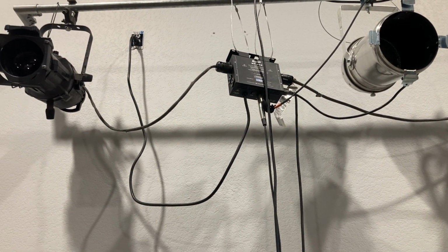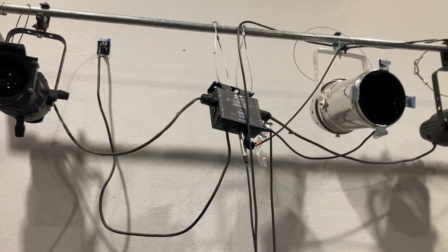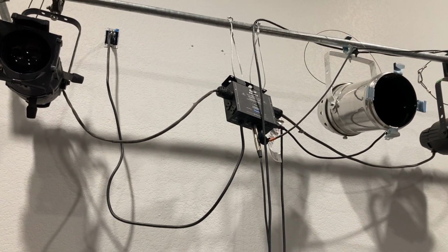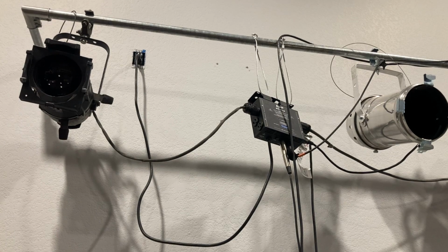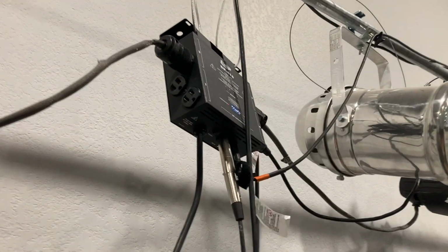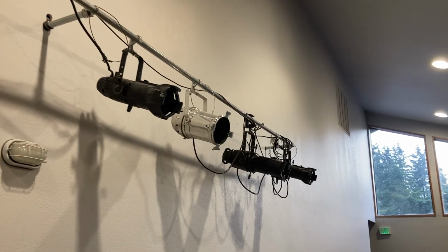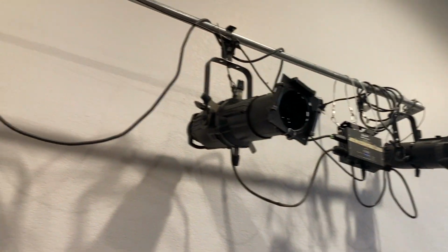And that's what connects all the power, or the dimmer, that's the dimmer. All the power from our can lights are connected to that. So that's how we run the can lights. We have the dimming capability. It's not just on and off power, and we control them by DMX to be able to do that. So this also has an adapter like the one on stage, just kind of the reverse. So it's a DMX cable run into that adapter, into the dimmer, which then has a DMX out all the way over to our other dimmer right over here. And that's how we control all of the lights up here.